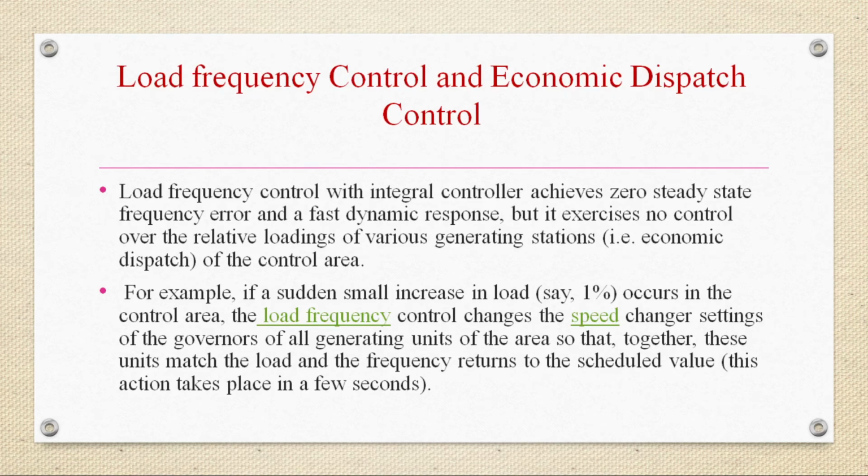Load frequency control and economic dispatch control. Load frequency control with an integral controller will achieve zero steady state error and fast dynamic response, but it will not have control over the relative loading of various generating stations of the control area. So what we are saying here is that we have achieved the case where steady state error is 0 and we are getting a fast dynamic response, but if there are changes in load, then there is no control over the changes in the load of various generating stations. That is the concept of economic dispatch.